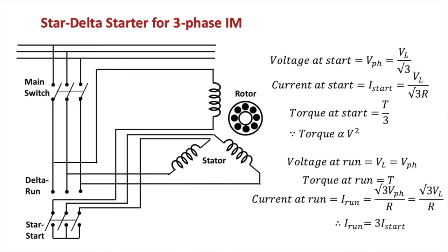So the star connection is only needed during the starting of the motor and not during the running condition of the motor, because at the run condition the current is already normalized, the inrush current is no more there, and so you can put it in the delta connection and have the rated torque output from the motor. It can be made automatic also.